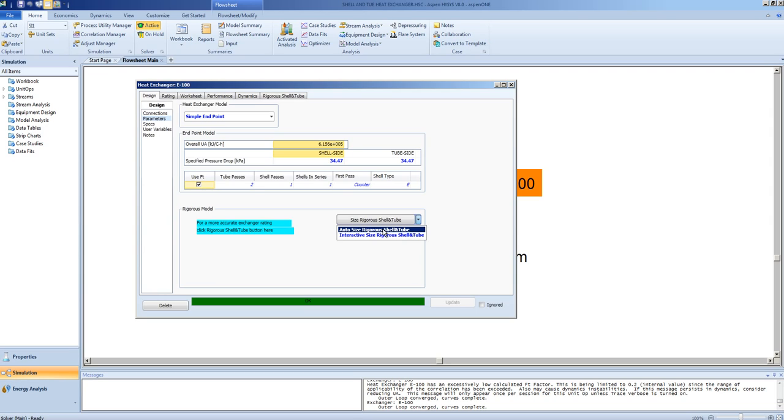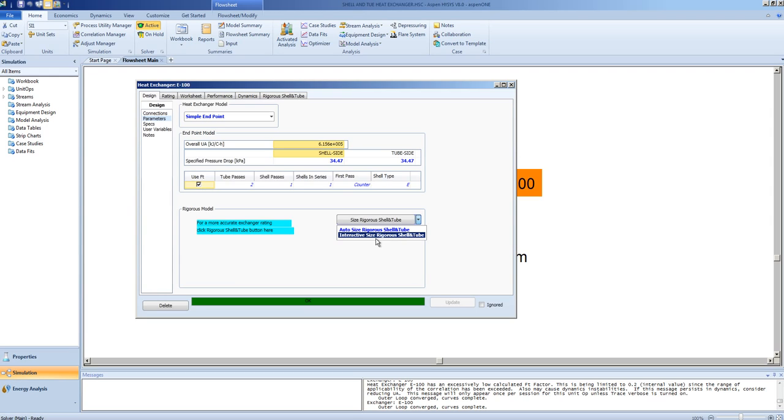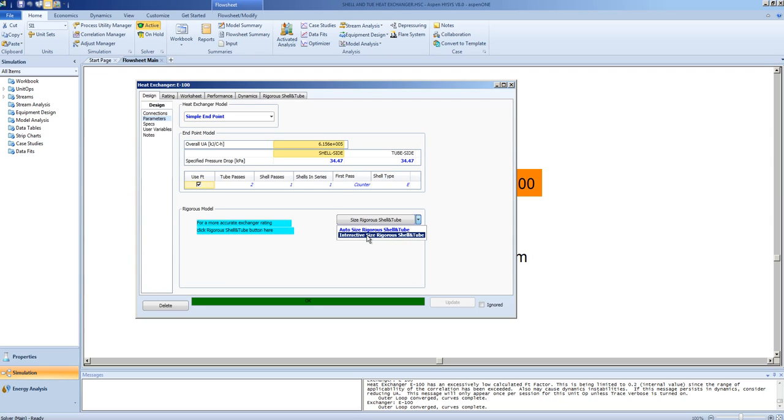We may also use the interactive sizing for the rigorous shell and tube. The difference between the two is the interactive allows us to set some of the variables that will be iterated upon. If you need to maintain an exchanger tube diameter of 1 inch or an overall tube length of 8 inches, choosing interactive allows you to set that and allow the other parameters to be calculated. We will use the AutoSize.